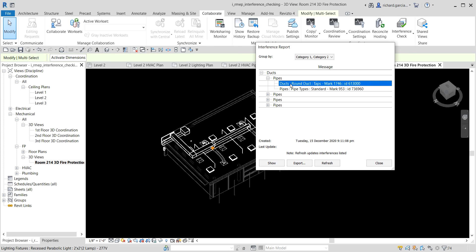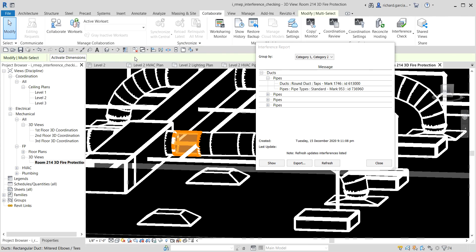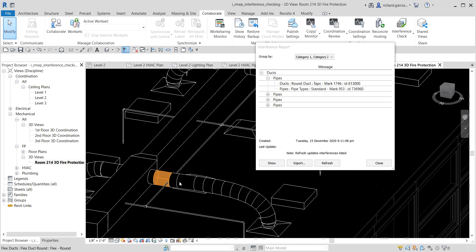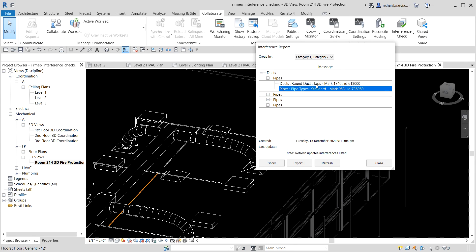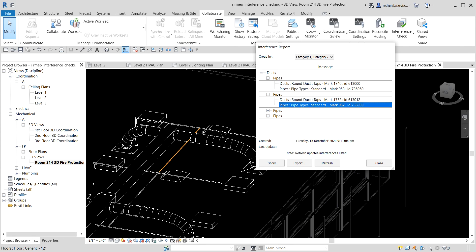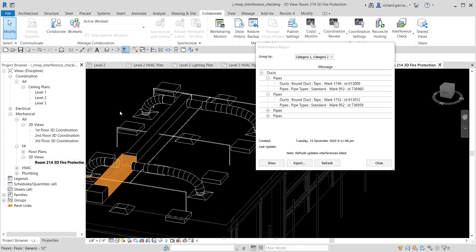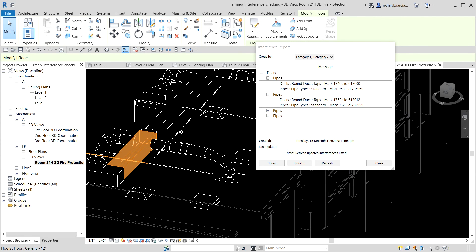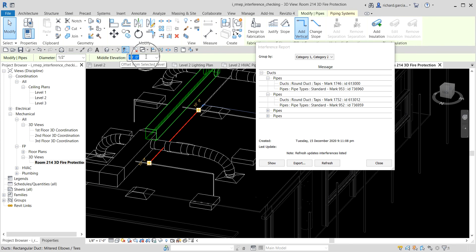There's a clash detected. Let me turn on thin lines and change the detail level to Fine — you can clearly see the clash between the duct and the pipe. To fix it, I'll click the pipe and change the middle elevation. Let's try lowering it to eight feet.